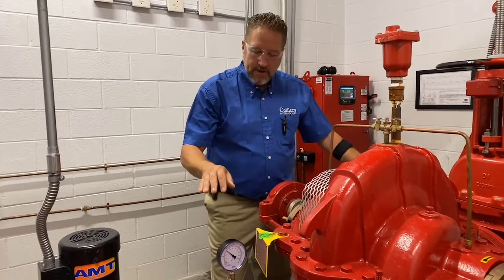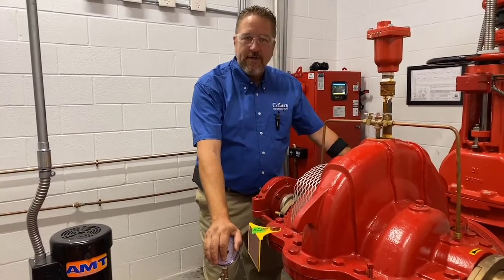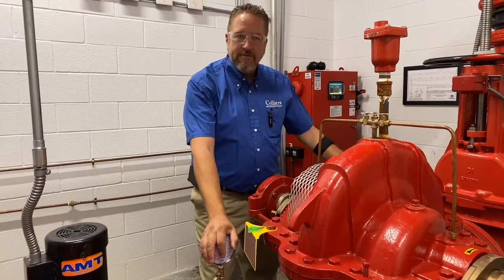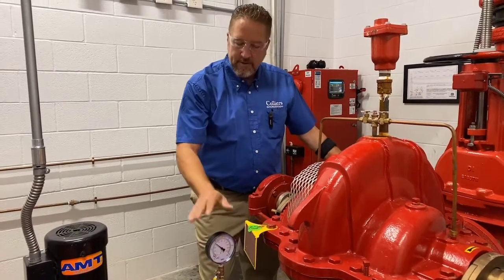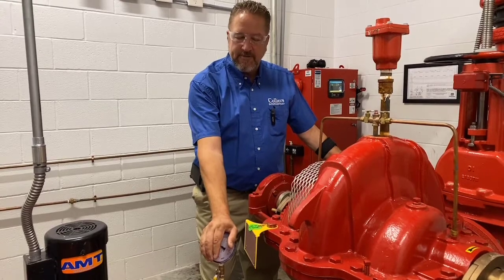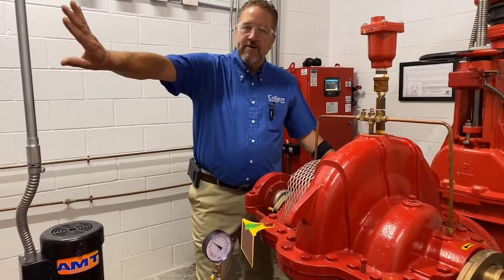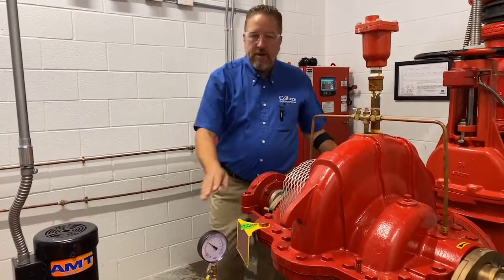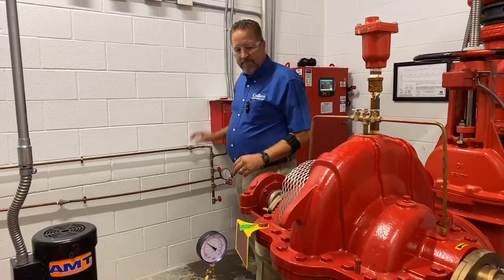Some of the other things you're going to look at is you have two gauges, one on each side of the pump. This one's coming in from the city. That's your inlet pressure. You have your discharge pressure on this side. This is what's going to your fire control system. So you're going to note that on your sheets as well.